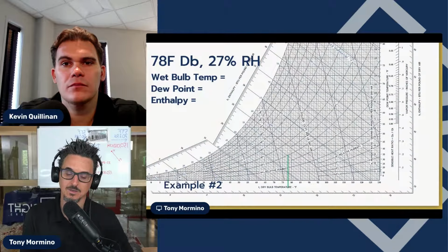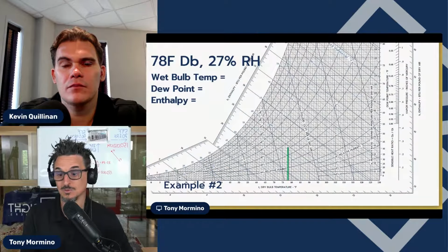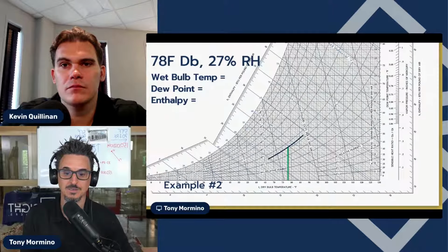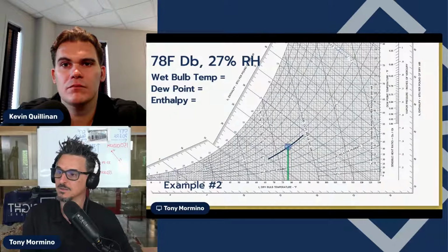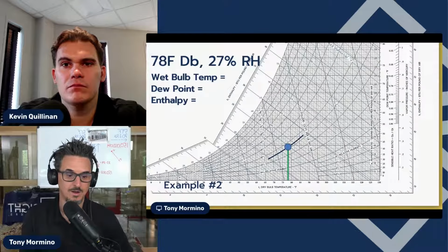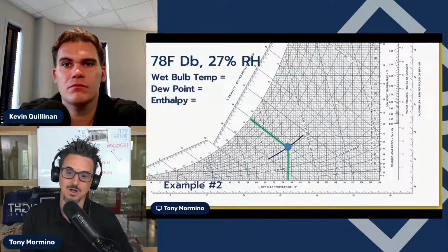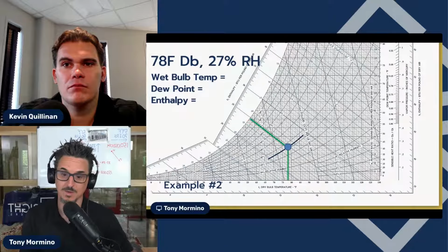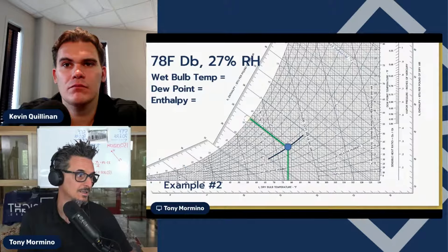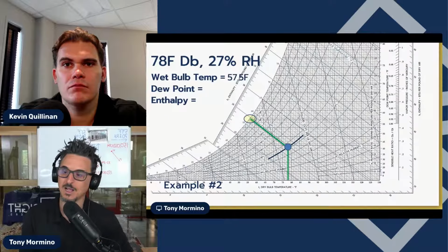So you would first plot the 2 known points, which is 78 degrees and 27% relative humidity, and then you get that point. Off of that, you could pull the other points. So wet bulb temperature, you follow the wet bulb line from that point to the saturation line. In this case, it's about 57 and a half to be exact.